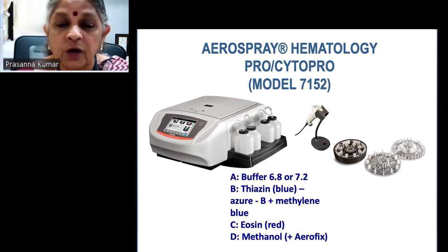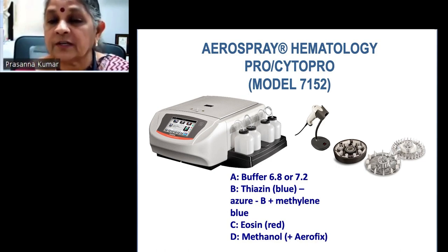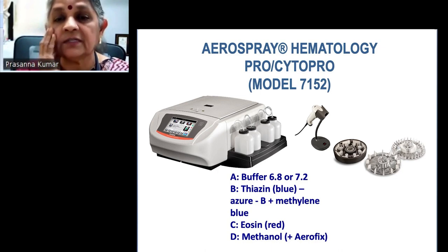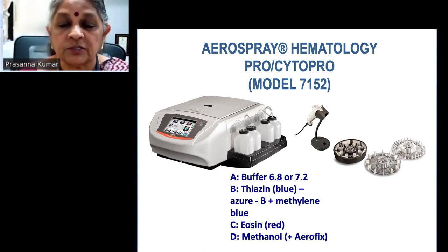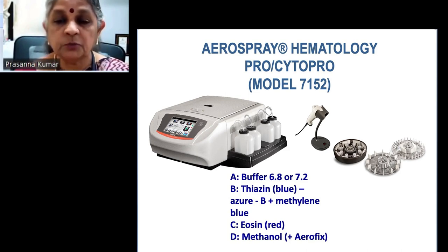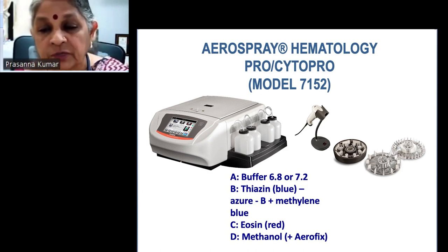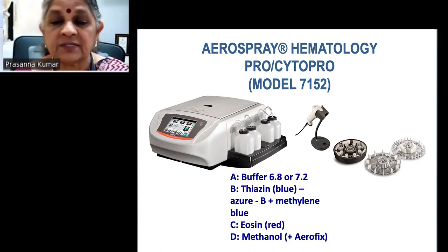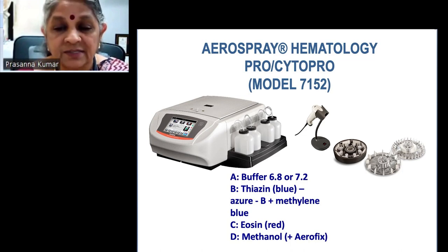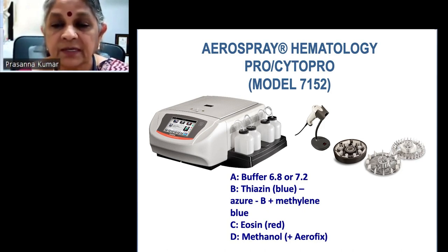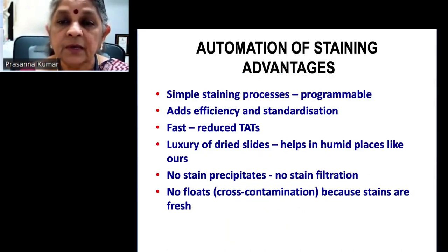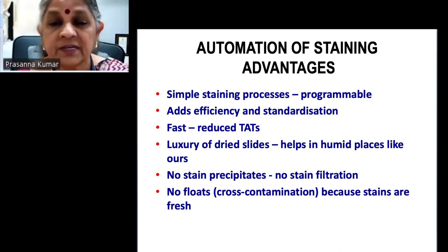After years of toggling with manual stains, we decided to invest in the Aerospray — a neat, automated hematology stainer. It uses a buffer with pH adjustable between 6.8 to 7.2, a thiazine stain — Azure B together with methylene blue — as well as eosin and methanol. These reagents are provided by the company. The automation of staining obviously has many advantages.